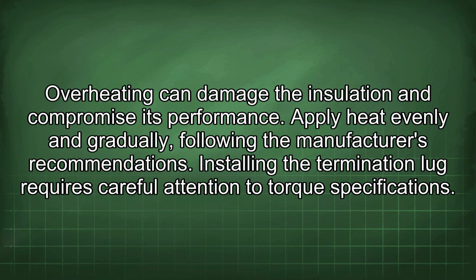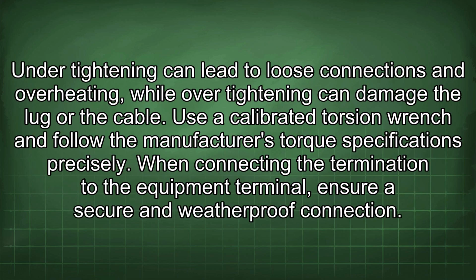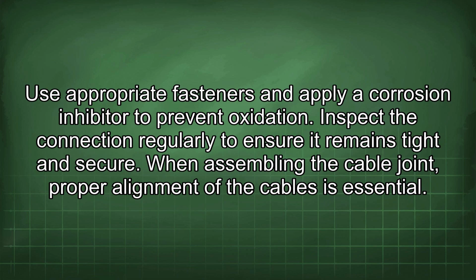Installing the termination lug requires careful attention to torque specifications. Under-tightening can lead to loose connections and overheating, while over-tightening can damage the lug or the cable. Use a calibrated torque wrench and follow the manufacturer's torque specifications precisely. When connecting the termination to the equipment terminal, ensure a secure and weatherproof connection. Use appropriate fasteners and apply a corrosion inhibitor to prevent oxidation. Inspect the connection regularly to ensure it remains tight and secure.